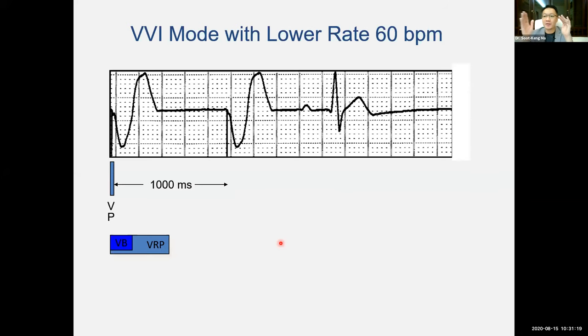So the pacemaker ticks for 1,000 milliseconds, tick, tick, tick, tick, until 1,000 milliseconds, not sensing anything, you deliver another pacing spike and initiate another ventricular blanking period here. And the cycle continues.